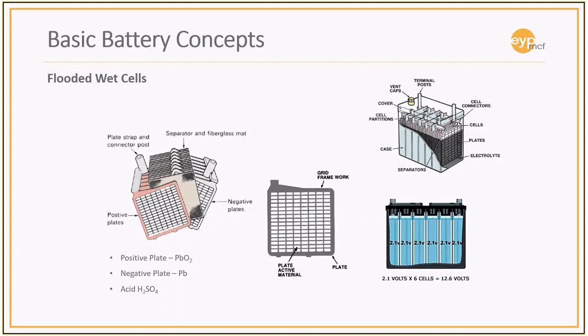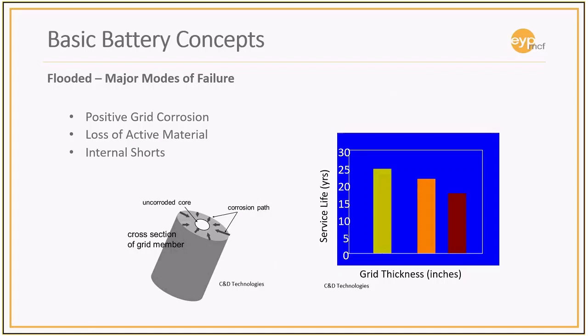Each of these cells is made up of a grid, or lead grid, or lead plate. These plates are interchanged as positive and negative plates with separators. The positive plates are usually a lead oxide, with the negative being pure lead. Then there's an acid, or sulfuric acid, that's used as the medium to transmit the electricity between the systems as the transfer material.